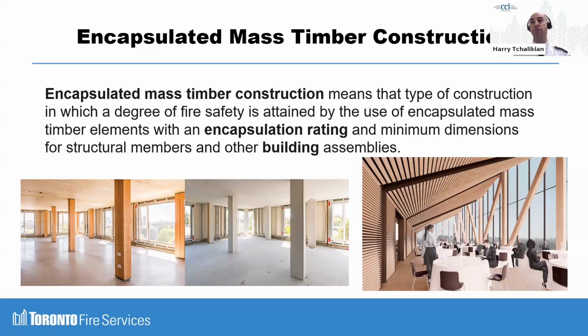So this is a new type of construction altogether. Most buildings are either combustible or non-combustible, and heavy timber construction was a subcategory of combustible. Encapsulated mass timber construction is similar to heavy timber, except the wooden members are larger. And the encapsulation is the fact that they are coated with drywall. If you look at the pictures at the bottom, where my laser pointer is, you should be seeing wooden columns. That's unencapsulated mass timber construction. It's being constructed, it's not encapsulated yet.